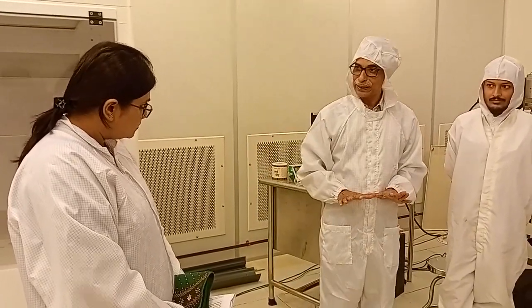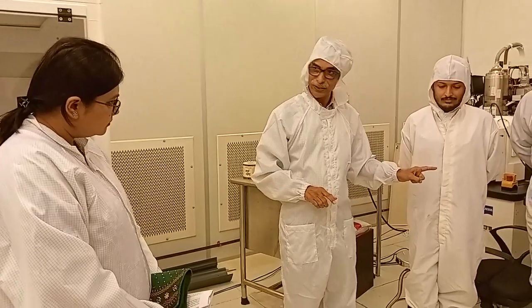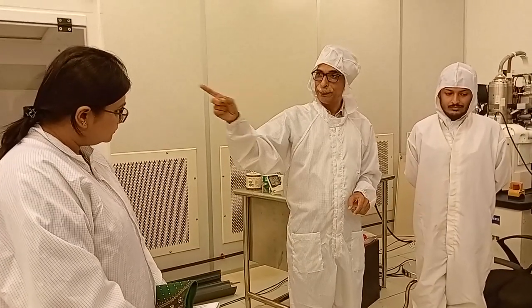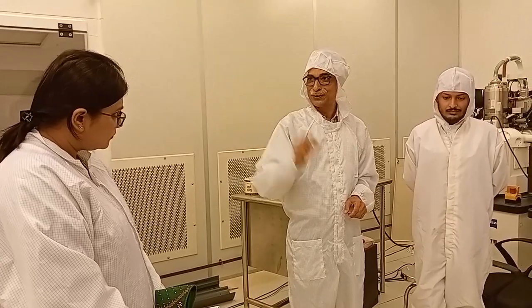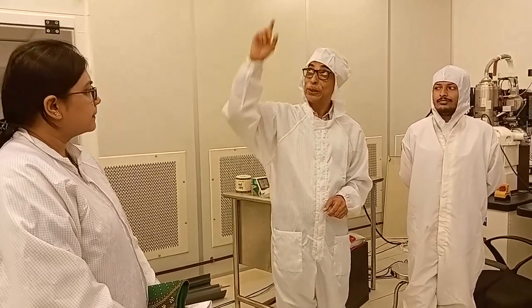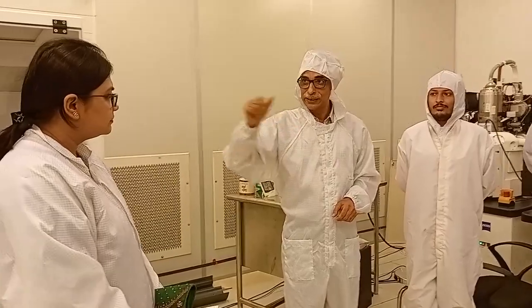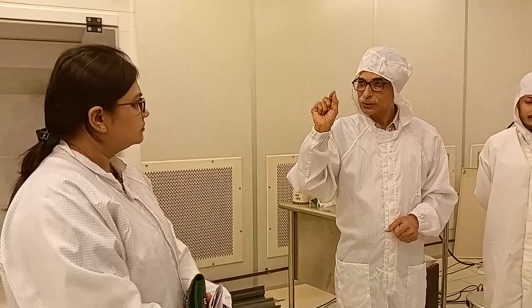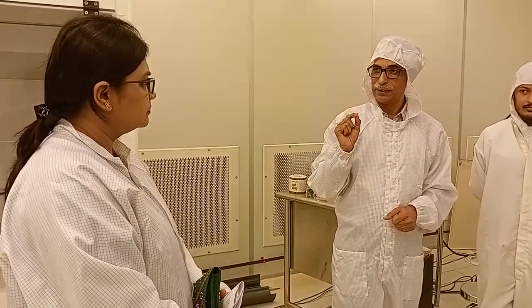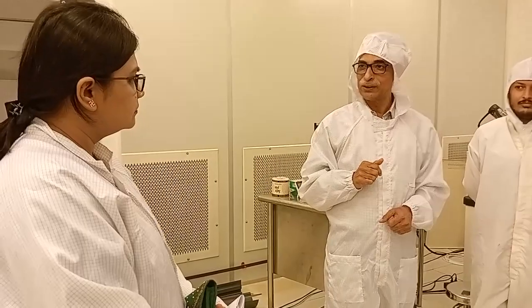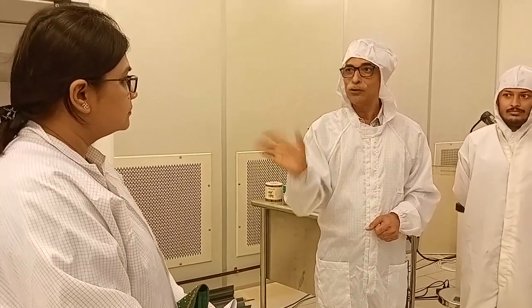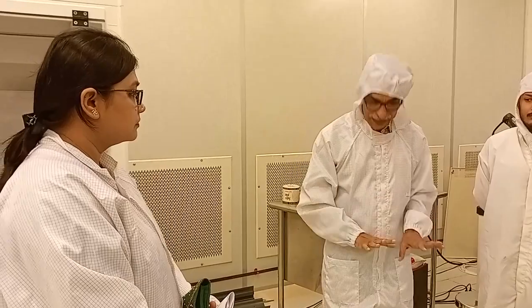So it's a completely separated block we are standing on, where this machine is located, because lots of buses, lorries, everything going through creates vibration. Even a plane flying overhead creates vibration. We are talking about precision on the order of 1 to 20 or 15 nanometers, so if vibration is of micrometer order, you will never grab the picture, it will be totally blurred. So it is a specially designed room and block so that no vibration comes in, which is why it's possible to take pictures of that quality.